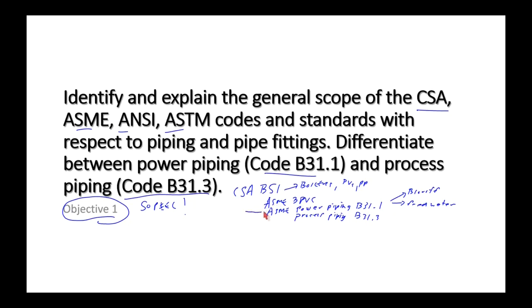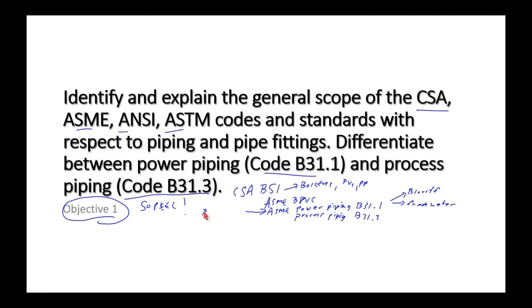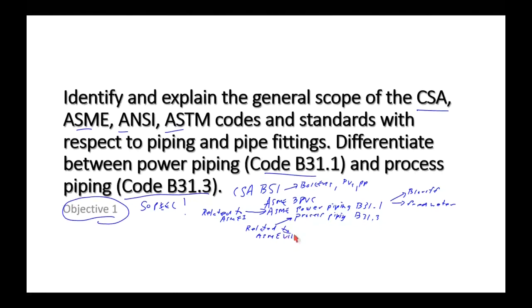You could relate power piping to ASME Section I, because it's really about boilers and high-pressure steam piping. Similarly, the process piping code is kind of related to ASME Section VIII — pressure vessels. These are crude comparisons, but the process piping code covers all kinds of pressurized fluids other than steam.